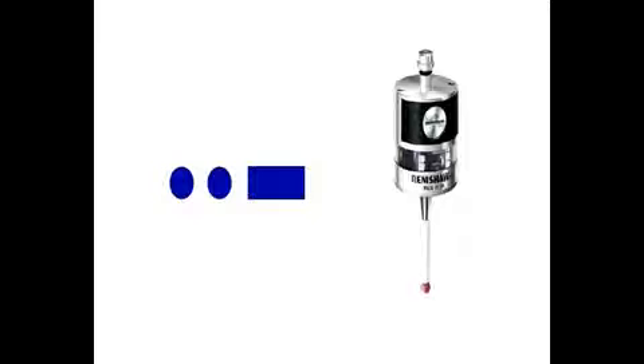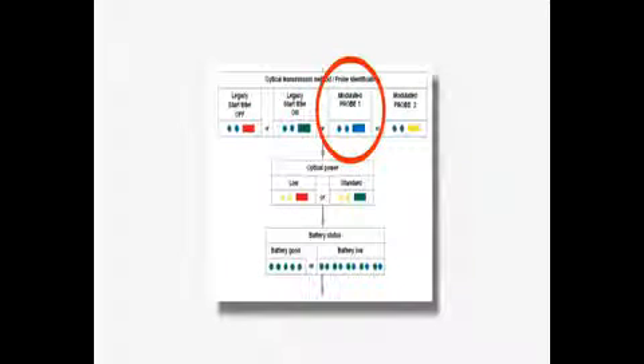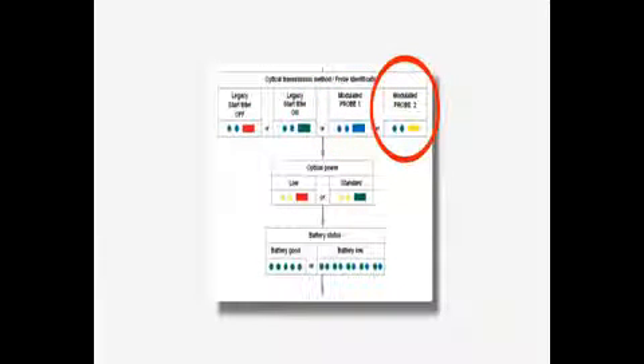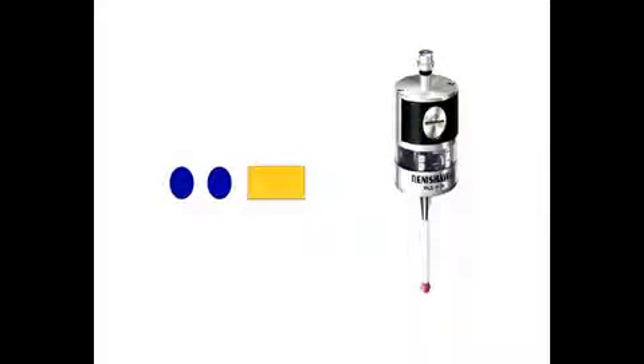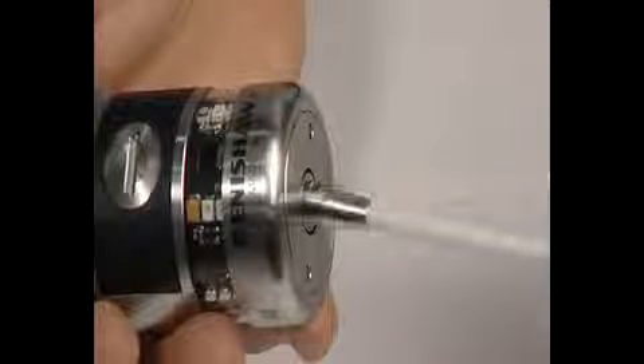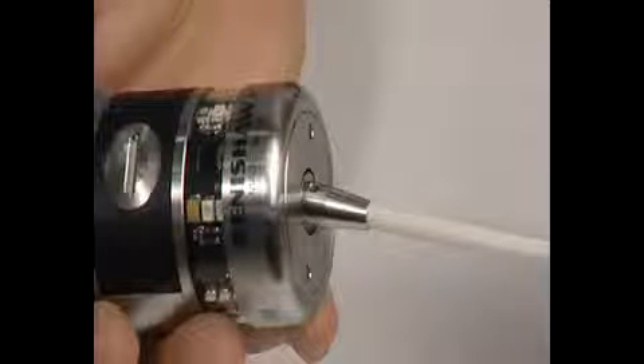Blue, blue, blue. Modulated transmission probe 1, for use with OMI2 and its variant interfaces, providing substantially increased resistance to light interference. And blue, blue, yellow. Modulated transmission probe 2, for use with the OMI2T and H variant interfaces when twin probe installations are required. Again providing substantially increased resistance to light interference. To move to the next option, the stylus should be deflected for at least 4 seconds.